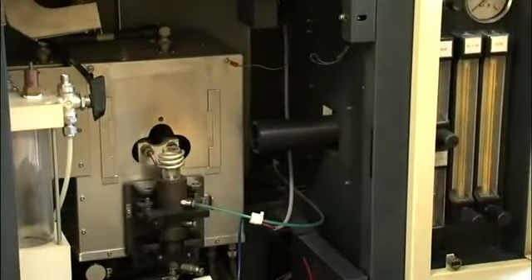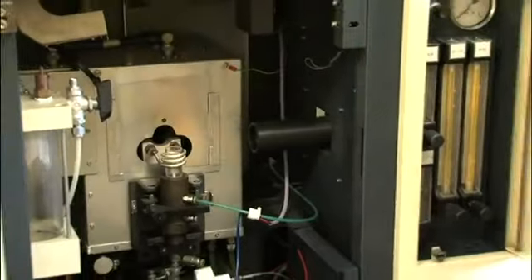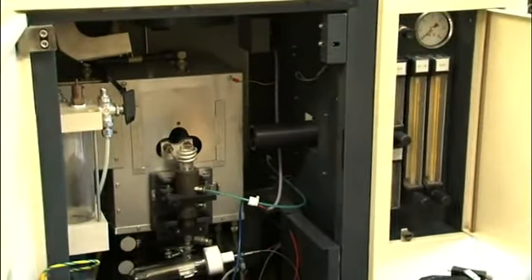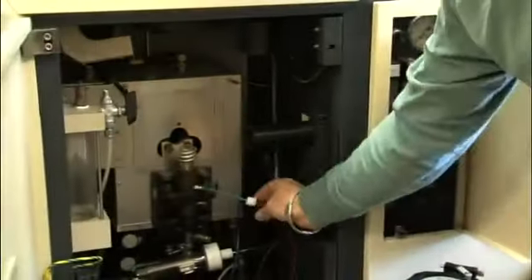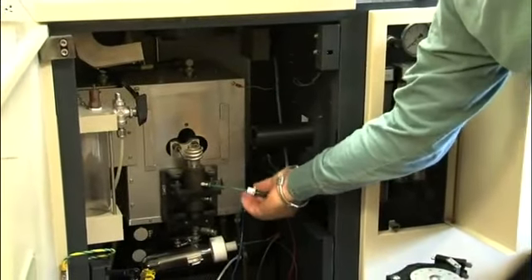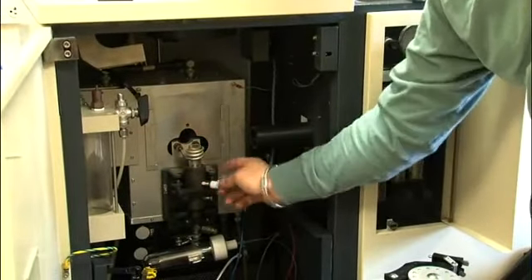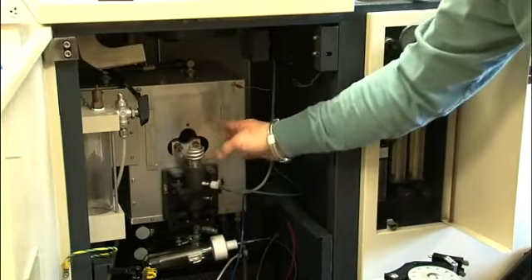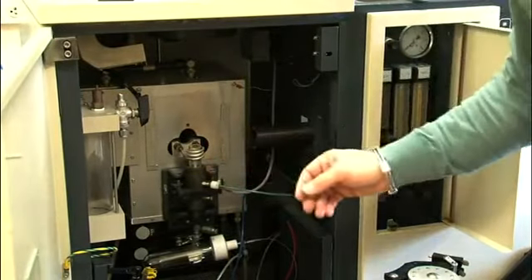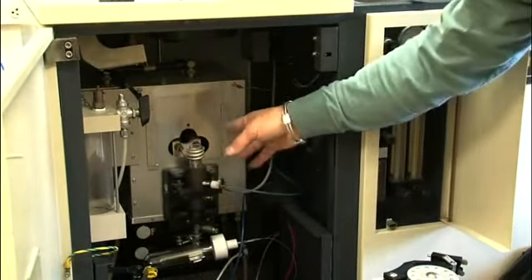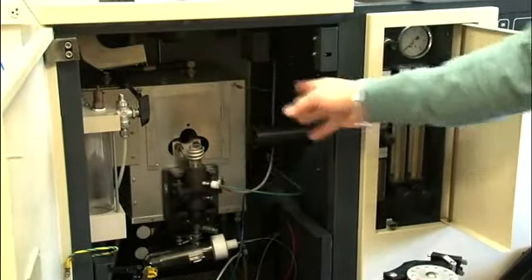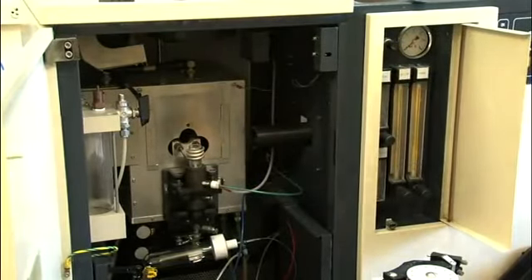Plugs into the top. Where was that diagram? Oh, there wasn't a diagram on here. But anyway, green corresponds to green. Green is on the top. This is your igniter wire. This sends an electric spark, follows the argon stream, and ionizes the argon gas. The coil's purpose is just to heat that gas up, 10,000 Kelvin. You don't want to get too close to that.